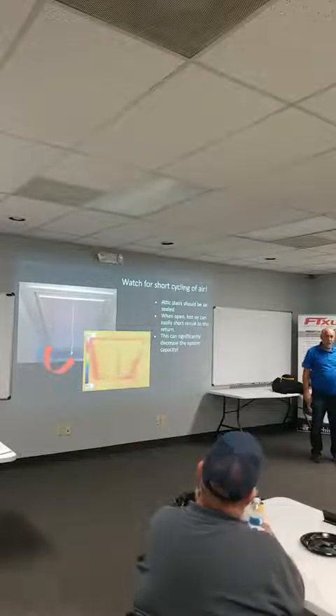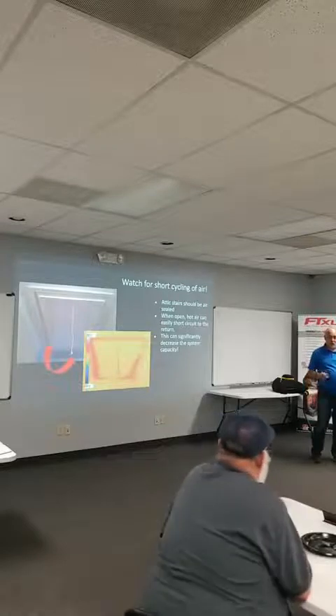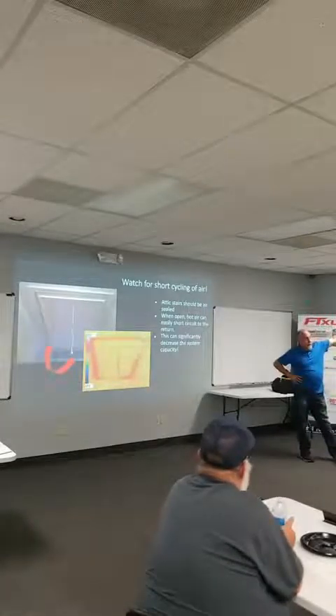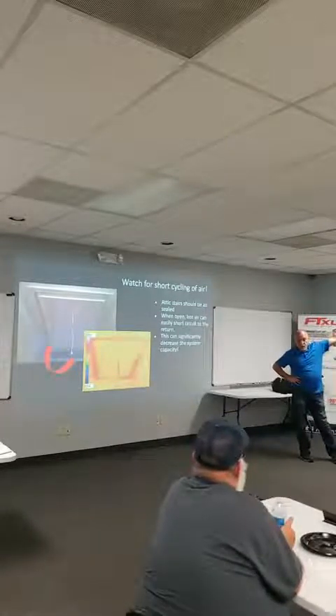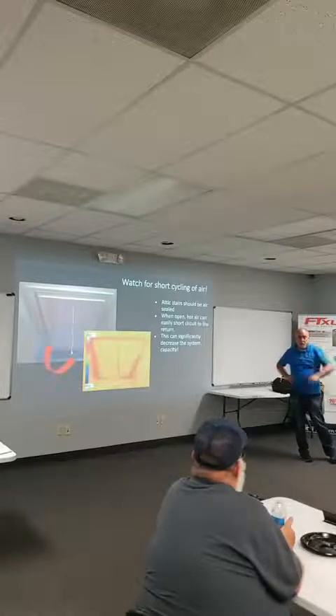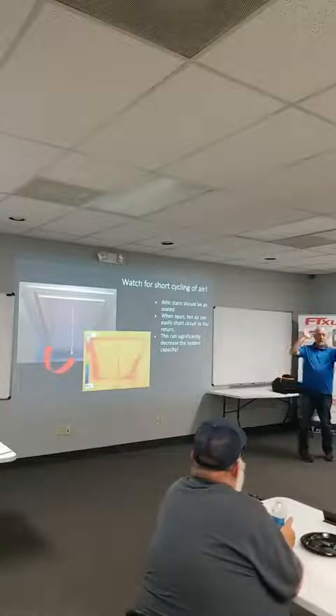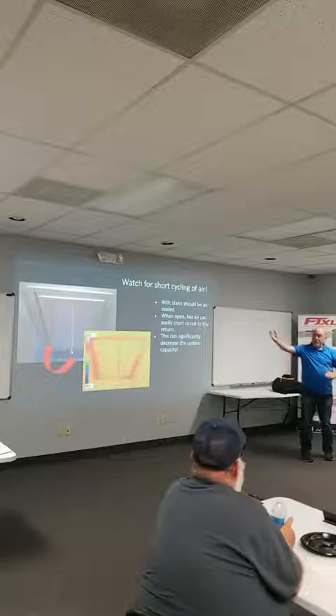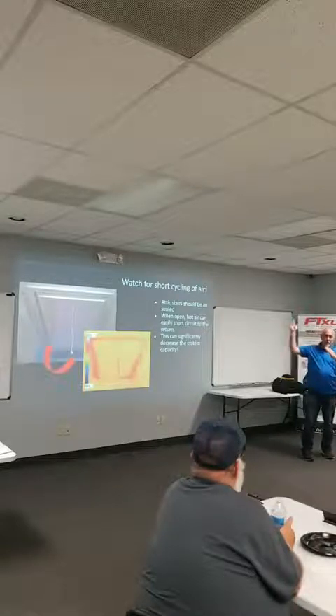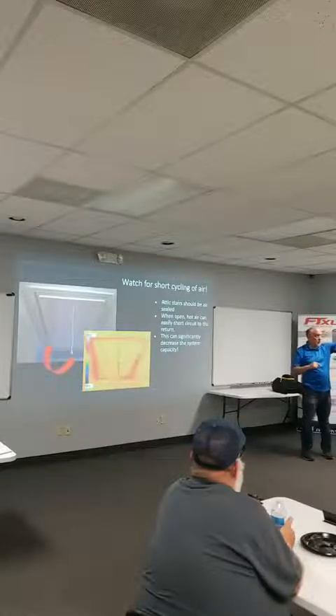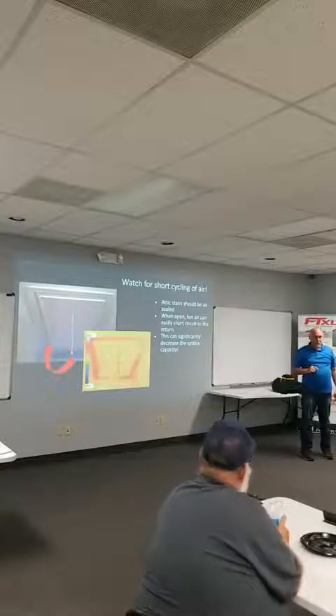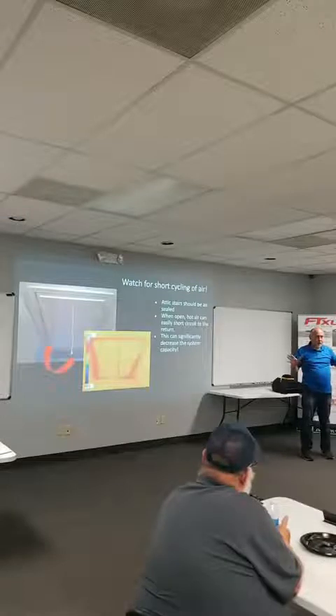In fact, this was something we learned when we designed our filtering system for our office. You put a high velocity system across the wall over here, so I can throw air clear across the room. When I throw air across the room in streams of air, guess what happens? The air around it actually gets entrained. When it's blowing through, it creates entrainment, and I pull the air back and I put my 2 filters in the back. So I have my returns in each corner and my supplies right in the middle here. And so all my ductwork's on the same side of the room, right? Completely counterintuitive to what you might think.